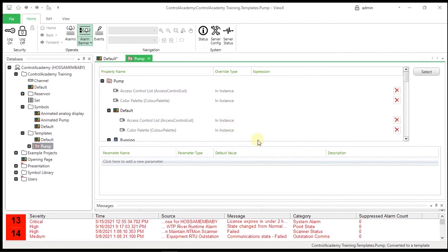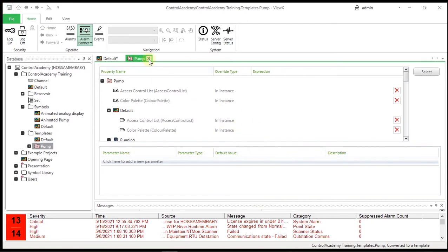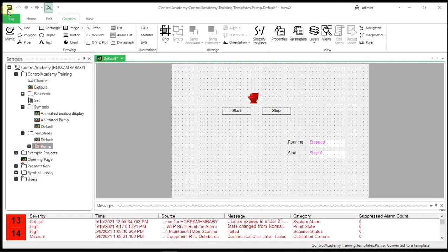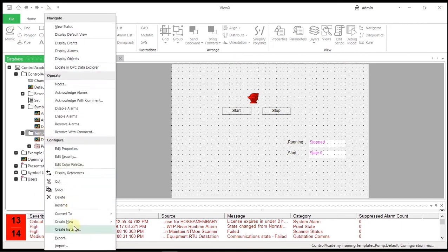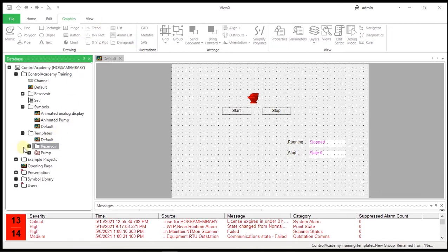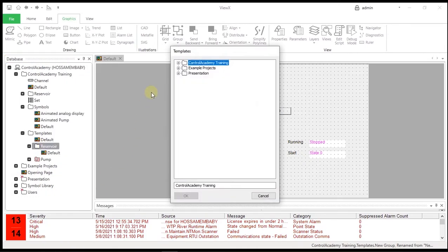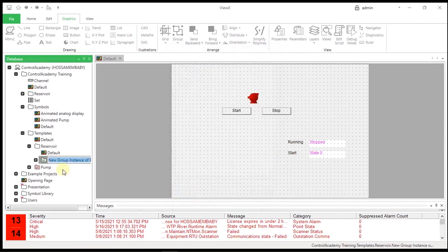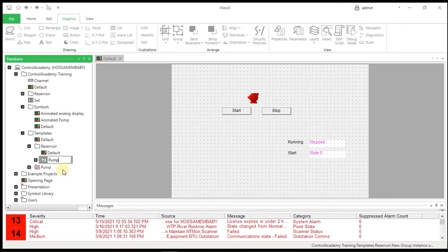Now that you have a group template, you need to create a template instance that can refer to the group template for its configuration. In the Templates group, create a new group named Reservoir. From the Object menu for the Reservoir group, select Create Instance, and then select the pump template. A new folder is created. The folder is green to indicate that it is a group instance. Name the instance Pump1.